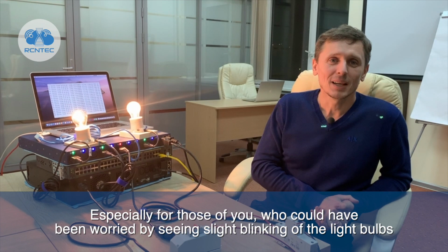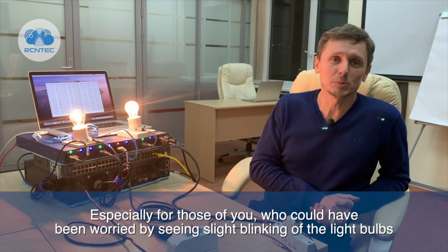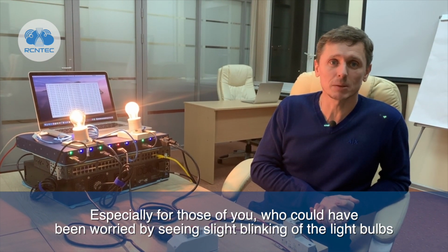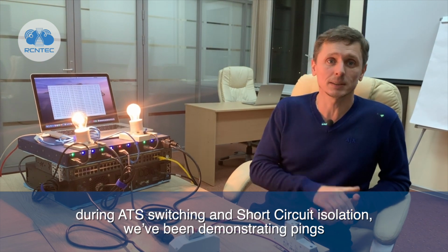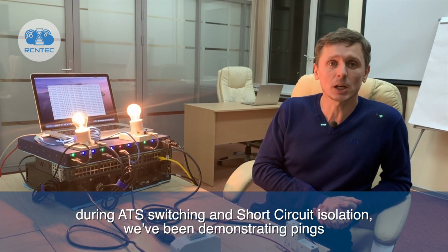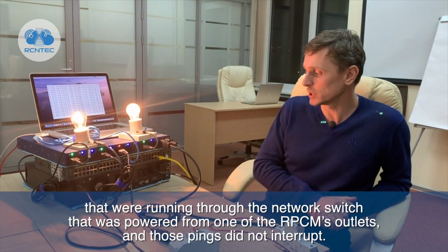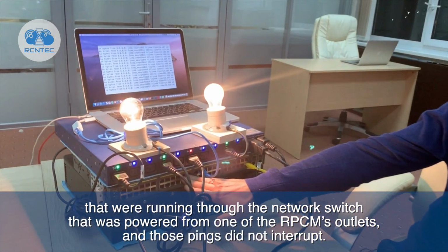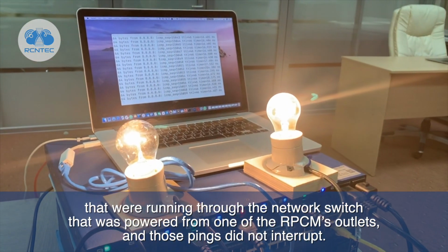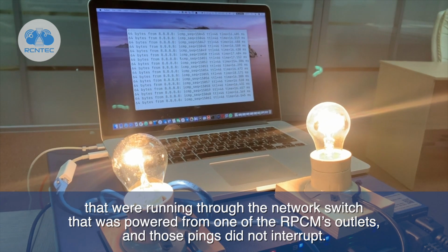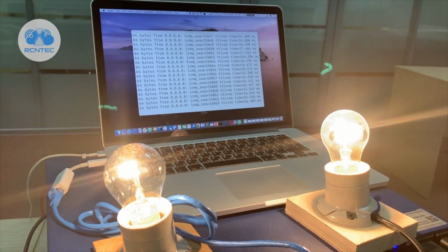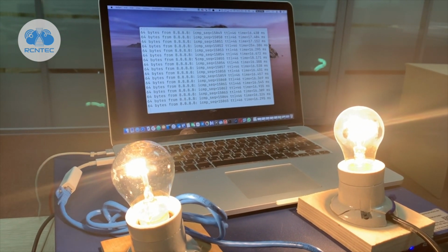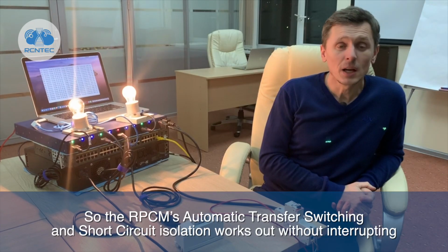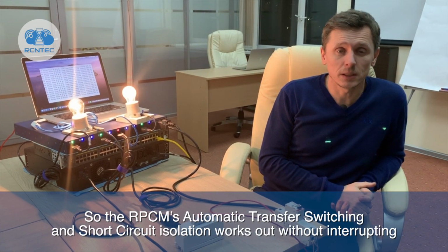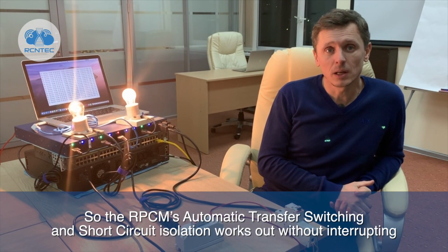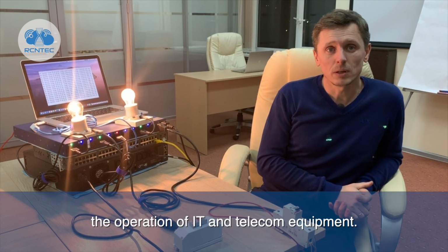Especially for those of you who could have been worried by seeing slight blinking of the light bulbs during ATS switching and short circuit isolation, we've been demonstrating pings that were running through the network switch that was powered from one of the RPCM's outlets, and those pings did not interrupt.